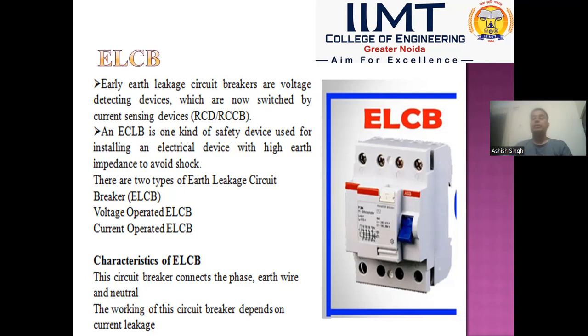Under abnormal or leakage condition, the incoming current is more than the outgoing current through the neutral wire, and so due to the potential difference, a current starts flowing through the relay, and this relay is actuated to send the trip signal, due to which ELCB trips. The main characteristic of the earth leakage circuit breaker is that it is connected between phase, earth and neutral wire. The working of this circuit breaker depends upon leakage current.